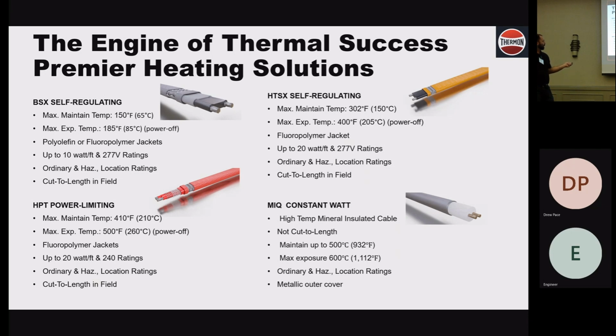I know here it says 410, and that's where you got to be careful. I saw yesterday there were some 455 temperatures listed on the heater cable - those are heater cable specs on a pipe. When you're in a bundle, you get one pass, and you're going to overheat that cable. In fact, you're going to overheat that cable if you try to get it to 410. So from our heaters, the max you can do is about 375 in a bundle comfortably. We have some you can push the limits on if you want, but that polymer starts to soften, and you don't want to do that.